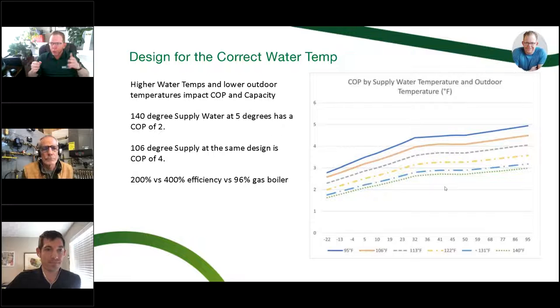It depends on what the outdoor air temperature is, and it also depends on what I am trying to make that unit do. Just to segue a little bit, that's where a water-to-water heat pump is superior. If you put a 5-ton water-to-water heat pump in, the reality is it's always a 5-ton unit. The ground temperature is stable and constant. It doesn't matter where you are in Canada or the United States. Somebody will dream up a spot in Alaska, but the reality is there are geosystems and research facilities in Alaska that are heating the space. I don't know if they're doing cooling, but heating the space just fine.